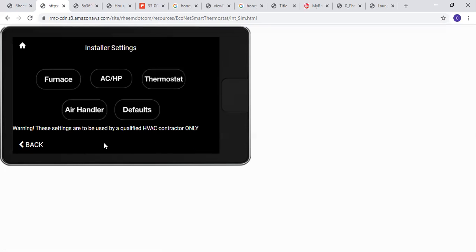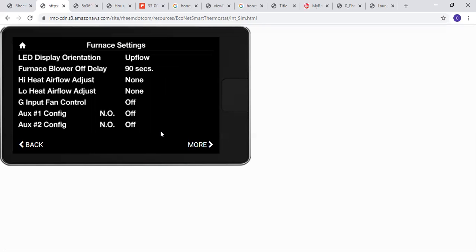Now, if you go to the installer menu here, so if we're going to set up a furnace, we talked about the dip switches earlier. So in this case here, if we have an R97 KSA, we need to go in here and highlight this one, change it to downflow. So our 7-segment display rotates. Here's our blower off delay, high heat airflow adjust, low heat. Our auxiliary 1 and 2, we can configure those.